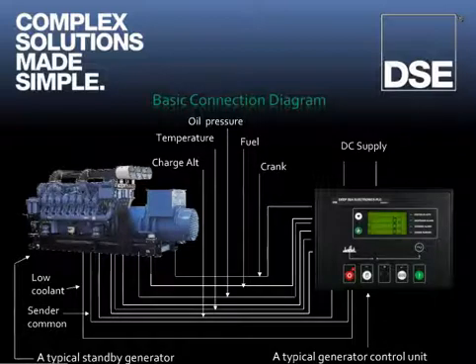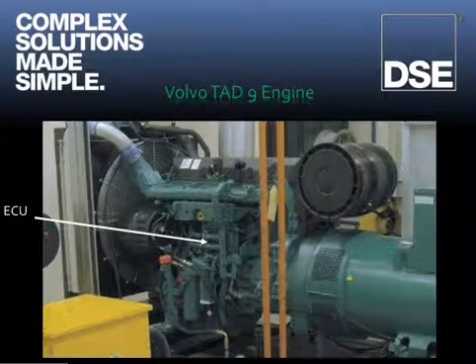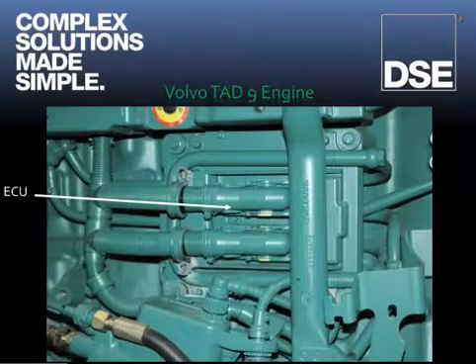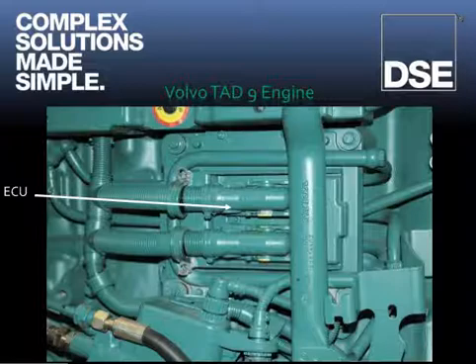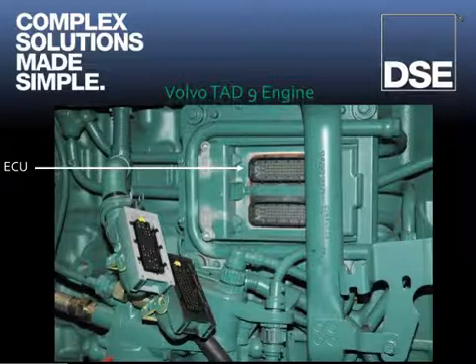This wiring, and much more, must be made by the generator assembler or panel builder. An electronic engine is fitted with a large computer called an ECU, that is connected to many sensors on the engine. These connections and sensors are fitted by the engine manufacturer. The engine ECU therefore measures parameters from many sensors to enable the ECU to finally control the operation of the engine and fuel injection.